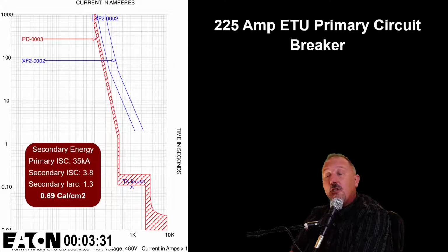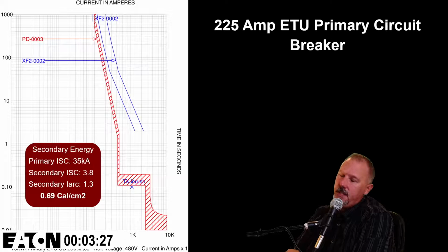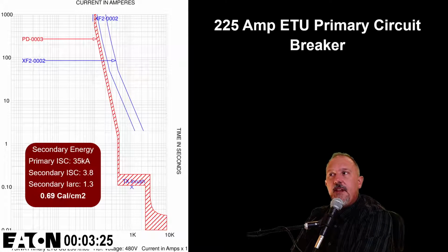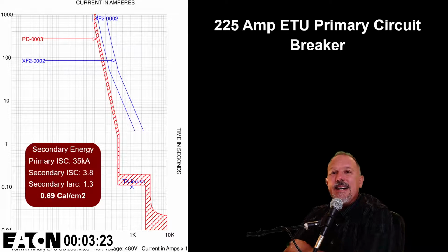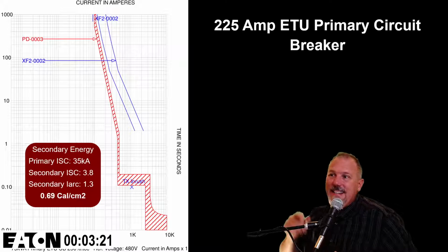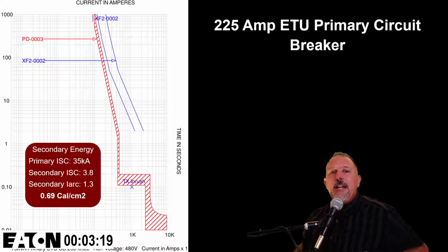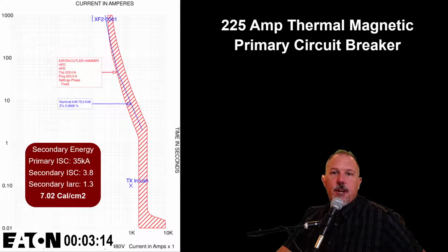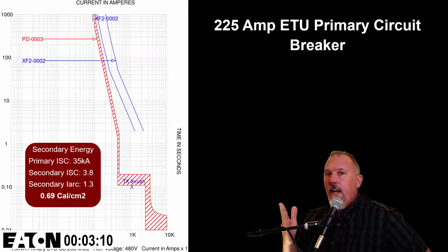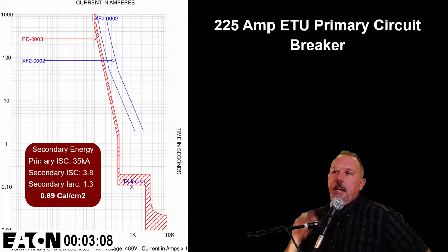Now, this is an electronic trip unit, 225 amp circuit breaker. I'm at 3.5 minutes, still doing okay. What's nice about the electronic trip unit is that knee that you're looking at right there. And you might say, well, why, Tom? The previous slide, I'm getting the job done. That's a standard thermal magnetic breaker. Why would I want to add more money to put an electronic trip unit in this application?